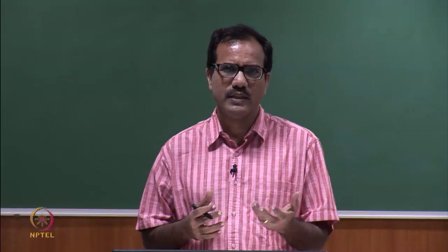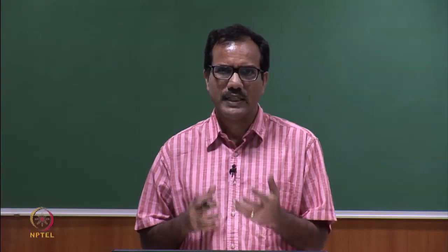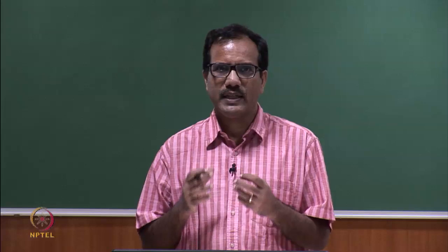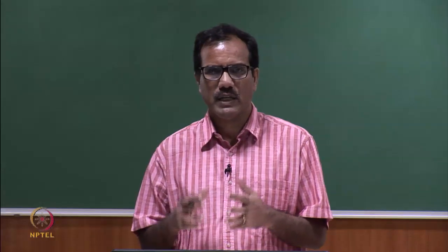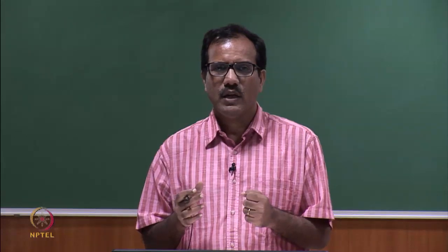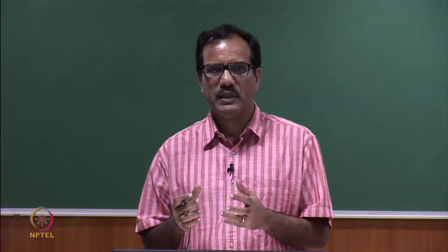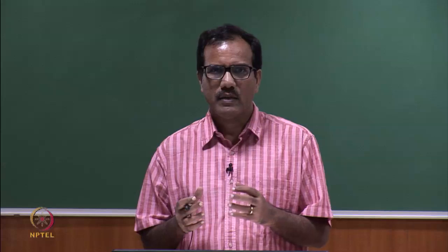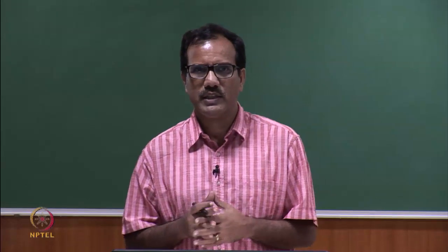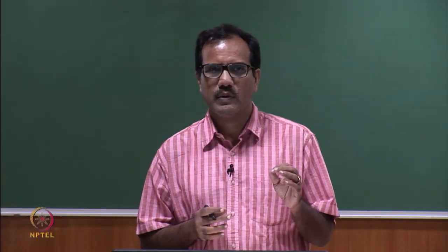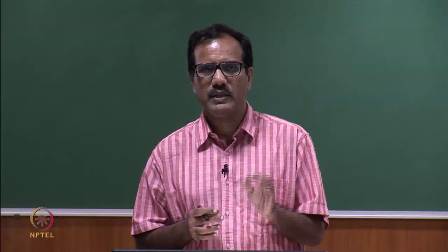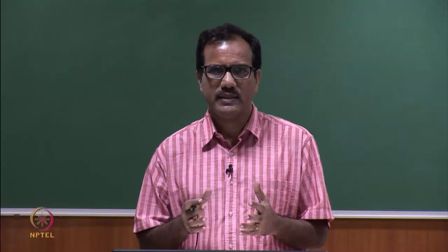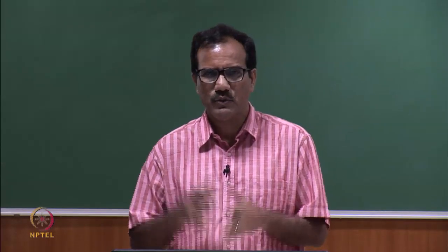So, why do we need the decay shape? Because if we analyze the decay shape, then we can resolve multi exponential decay. If there is more than one fluorophore in the system, then your decay will be multi exponential, and if we do not have the decay shape, we cannot resolve it. So, one must be able to temporally resolve the recorded signal at least to such an extent that the decay is represented by some tens of samples.